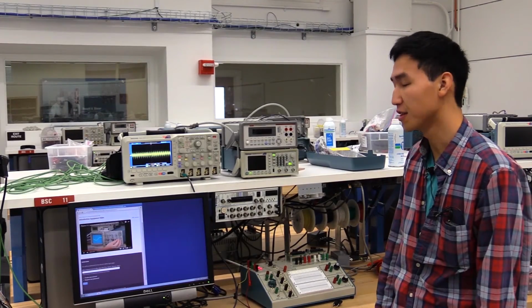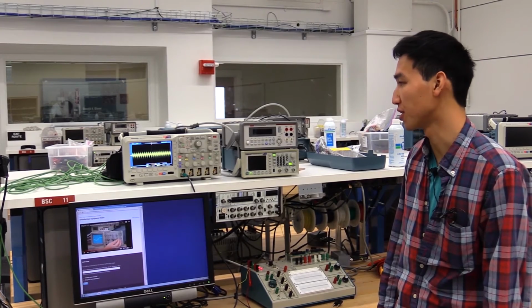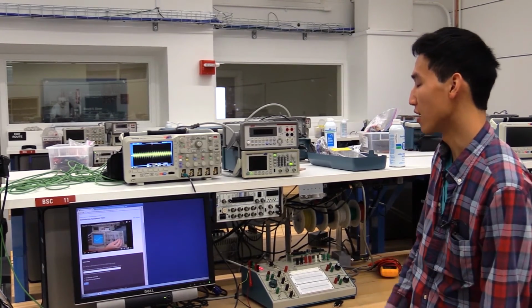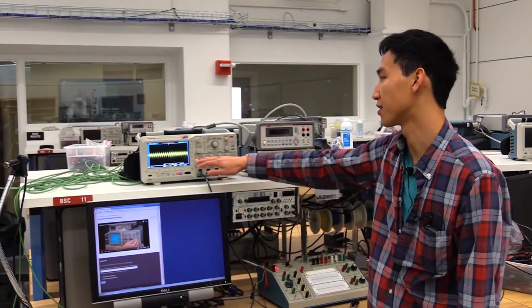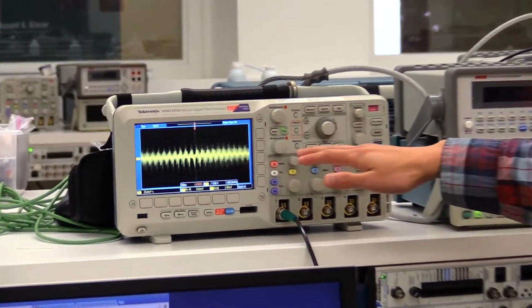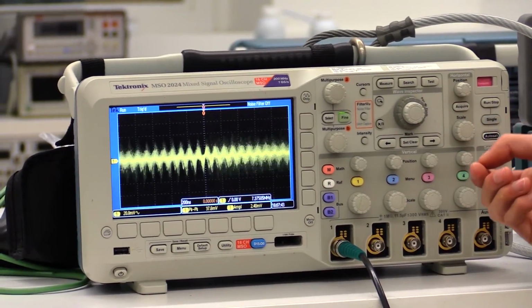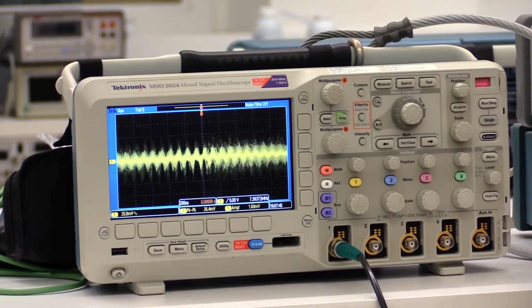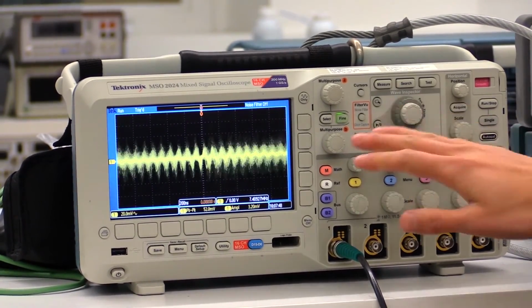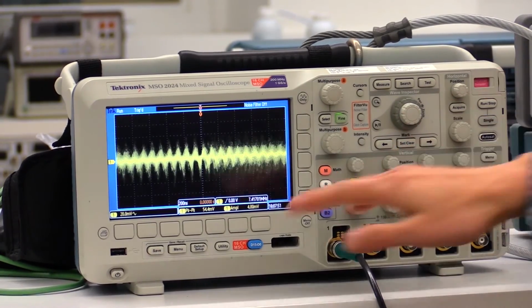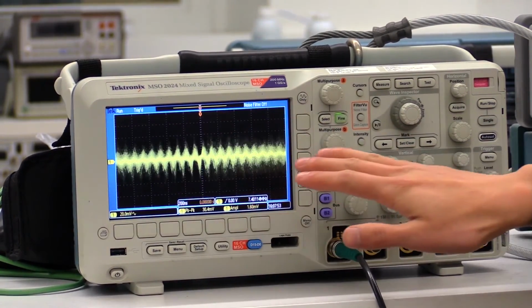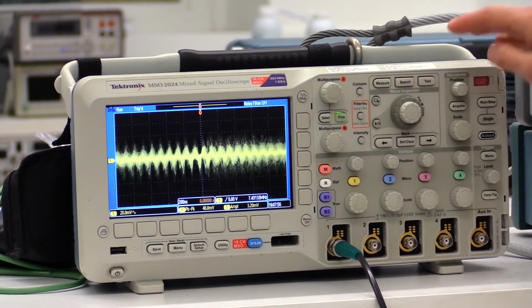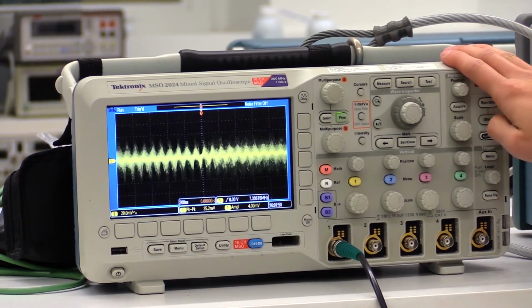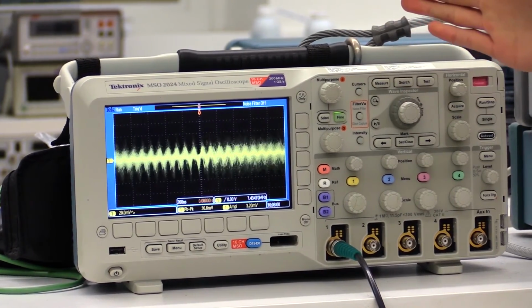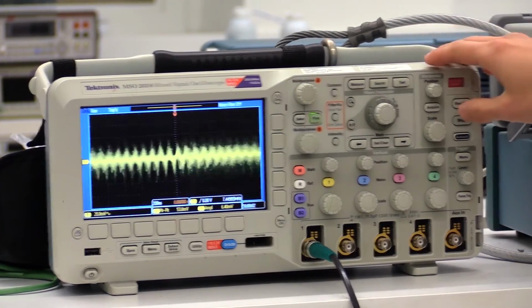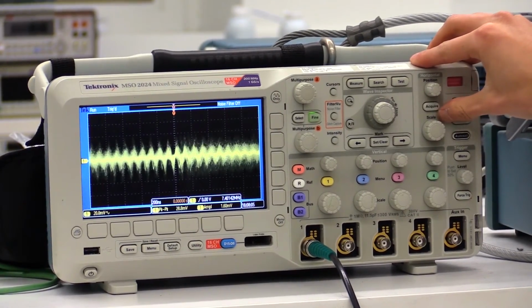Another advantage of the digital oscilloscope is its ability to average a signal. If you're taking a measurement of a signal and it's very noisy, such as this one, and there's absolutely nothing you can do to clean up that signal, and you know that it's a constant period and it's triggered well, and you can see that it's not changing over time, you can do something called averaging, which will take the average voltage of each spot and condense it down to the trace.